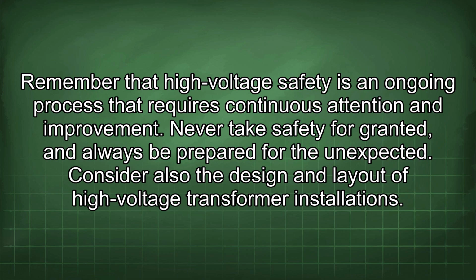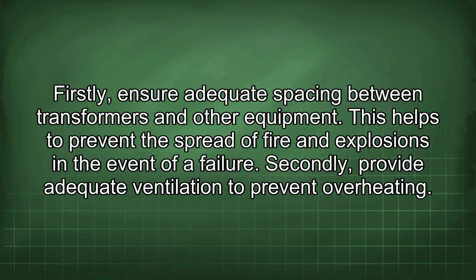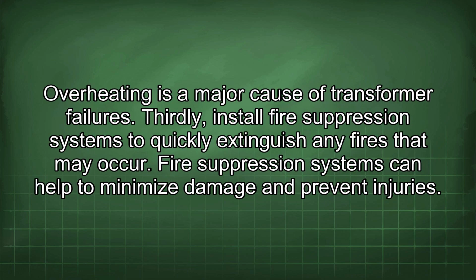Consider also the design and layout of high-voltage transformer installations. Firstly, ensure adequate spacing between transformers and other equipment. This helps to prevent the spread of fire and explosions in the event of a failure. Secondly, provide adequate ventilation to prevent overheating. Overheating is a major cause of transformer failures.